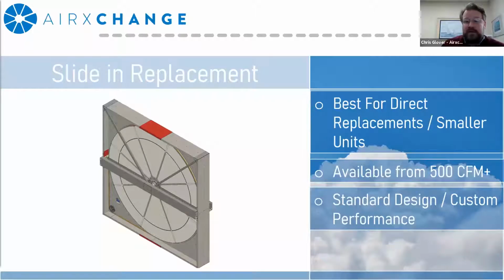So these are available typically between 25 inches in diameter to 74 inches in diameter, but that's not a limiting factor there on the upper end. They can go larger than that, as long as you're not concerned with the overall size and weight of the device. And the typical airflow range is between 500 CFM to about 13,000 CFM, which is where you see most of these being used. And once again, because there's no assembly of the device on site, these can be quite cost effective for certain applications.